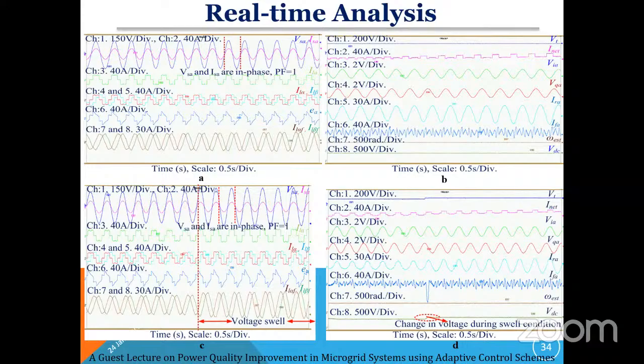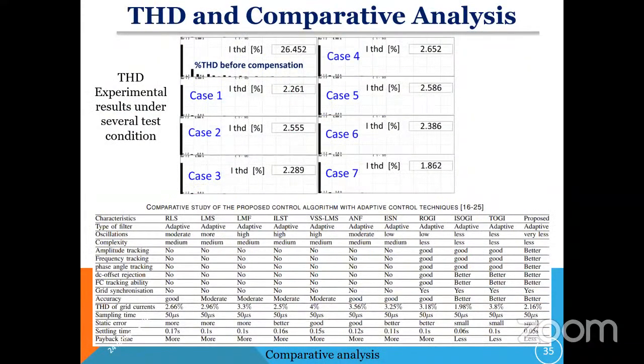And this is the real-time THD analysis. You can see the real-time THD analysis. Here in the experiment, we have used an uncontrolled bridge rectifier circuit. Before compensation, we get 26.452%. In case 1 we got 2.261, case 2, 2.555, case 3, 2.289, and for the remaining cases 4 to 7, we got less than 3%. So all 7 conditions, we have verified 7 test cases.